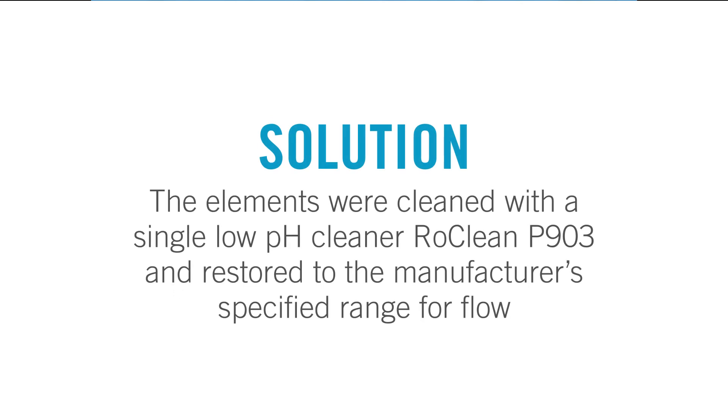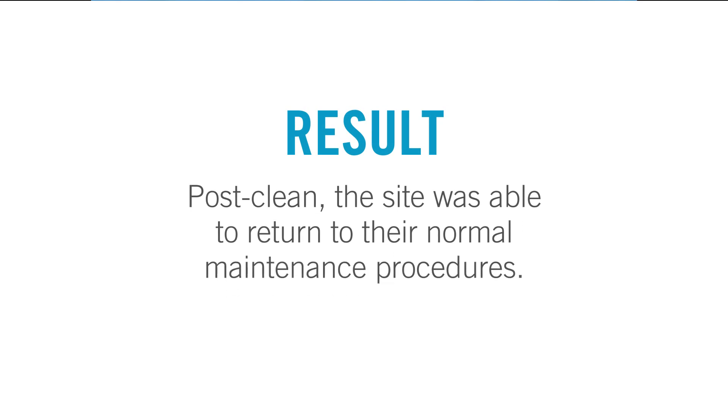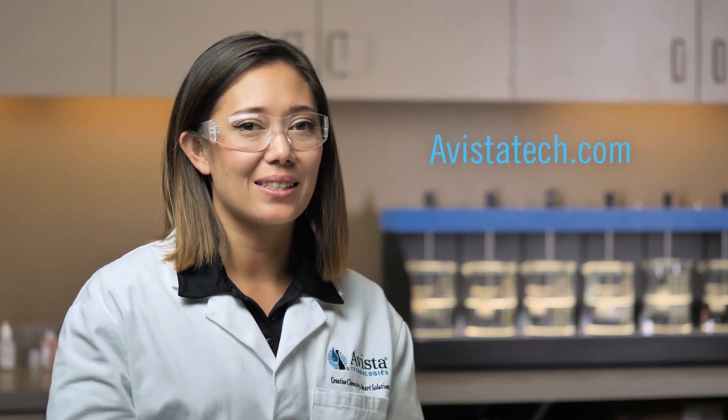In addition to solving the bypass issue, the elements were cleaned with RoClean P903, a single low pH cleaner. This restored the system to baseline performance, including dropping delta pressures by 10 psi per element. Post-clean, the site was able to return to their normal maintenance procedures. The key takeaway is that the autopsy provided us with invaluable information. Without it, the site would have continued to misdiagnose their issue as biological fouling rather than iron. The site is now back up and running and we are pleased to say that iron is no longer a fouling concern. Thank you for watching. For more information, please visit avistatech.com.